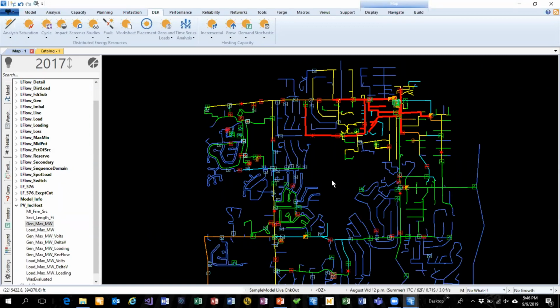Now we've got work to do. There's a lot of stuff we do in hosting capacity, we're handling substations, switch caps, tap changers, all sorts of things. But let me talk about two things we need to do: zero sequence impact, so ground fault current impact - I think a lot of you have 10% thresholds on that - and then relay desensitization. Both of those are on the protection side, we'll get that in there.